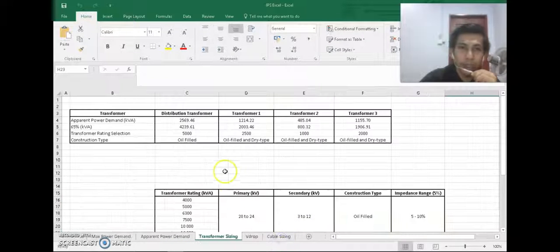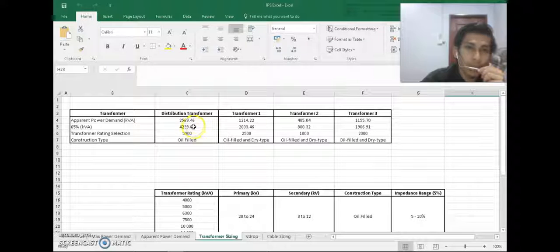Okay, then we calculate the transformer, which is the distribution transformer. We get the apparent power demand, which is 2569.46, and this is 65% of the kVA. Then we get the transformer rating selection, which is 5000. For the main transformer, the construction type is oil filled. The other three transformers are the same type, oil filled and dry type transformer.